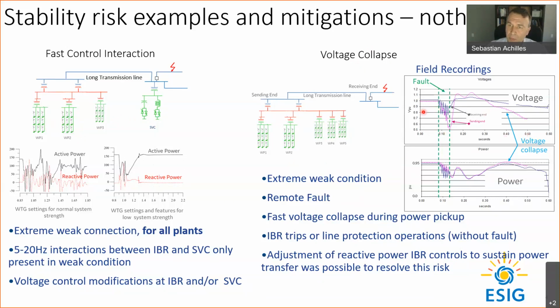You can see the upper plots are voltages. The pink is the sending end, and the darker line is the receiving end voltage. And then the lower plots are active power, again, receiving end and sending end. What you can see is that between the green lines, there is a fault. As a consequence of the fault, the wind turbines reduce the active power to reduce the risk of collapsing voltage during the fault and having trips during the fault.